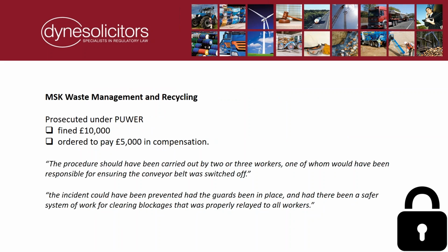Then we have another case, MSK Waste Management and Recycling. This is, well, a relatively old case. This was sentenced in 2013, and the first thing I would say is these fines seem very, very low. What happened here was that a worker lost his arm after trapping it between a roller and the belt of a moving conveyor whilst attempting to clear a blockage. Essentially, this machine was running while he was doing it. It hadn't been switched off, nor had it been locked off.